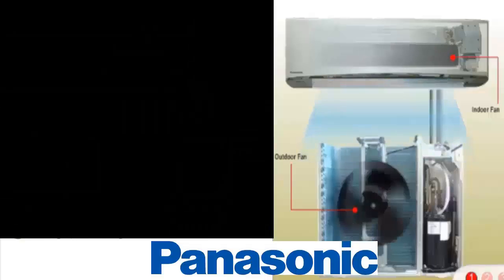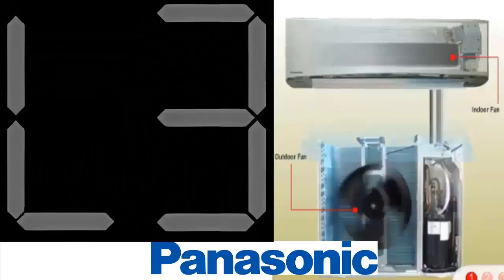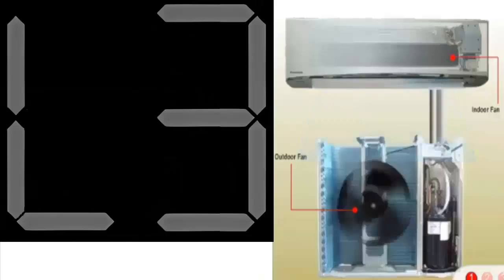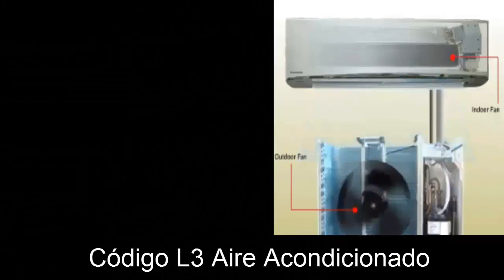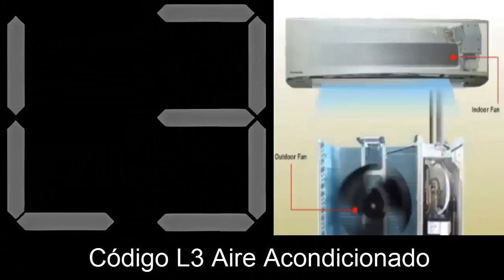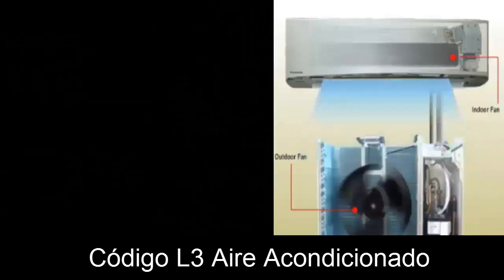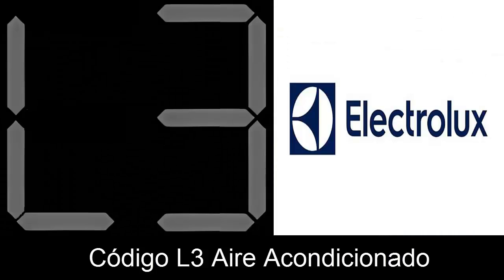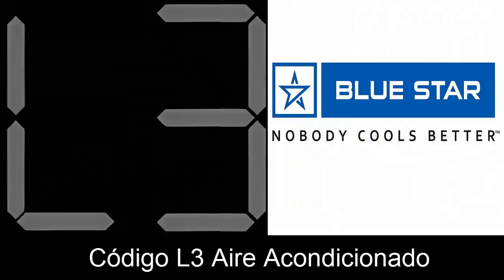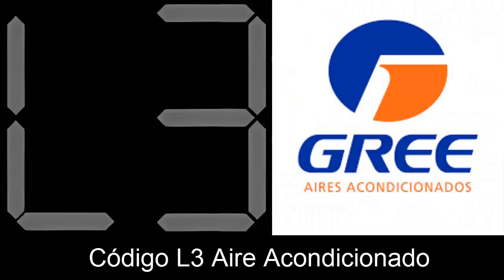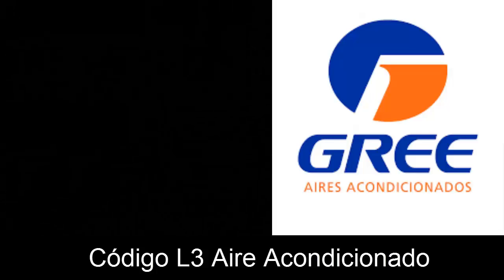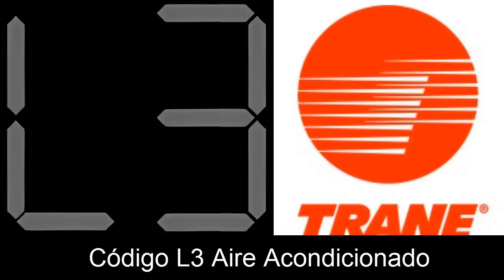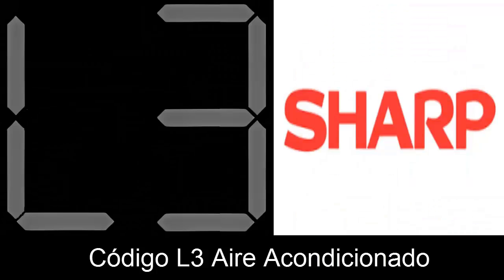The error code L3 in air conditioners generally indicates issues related to the external unit's fan. This error is common in many brands, including Electrolux, Bluestar, Gree, Trane, Sharp, Mundoclima.